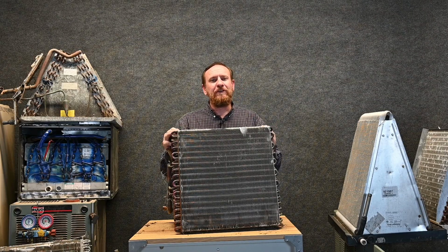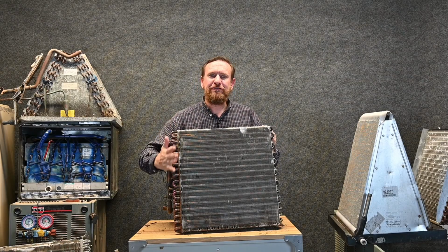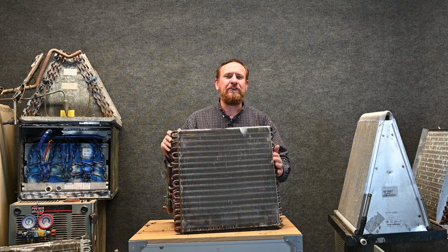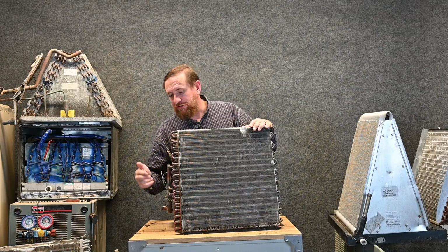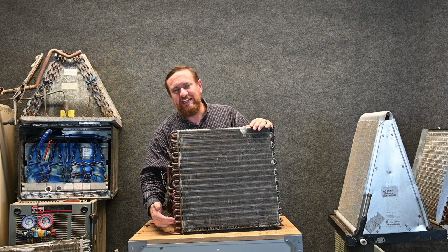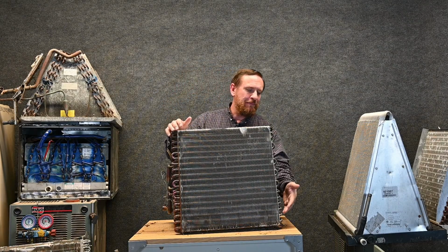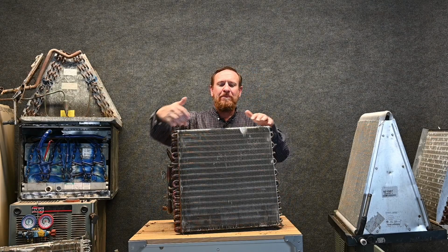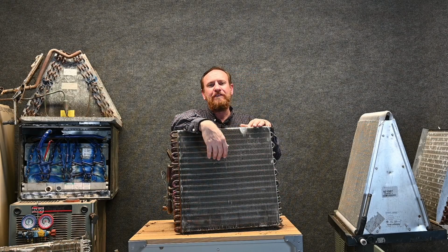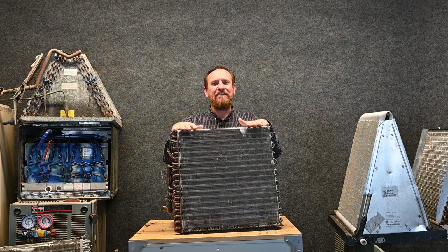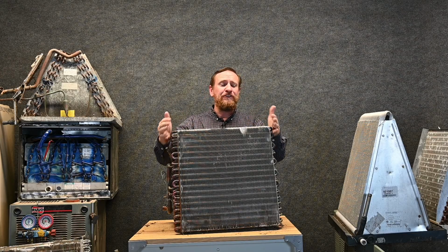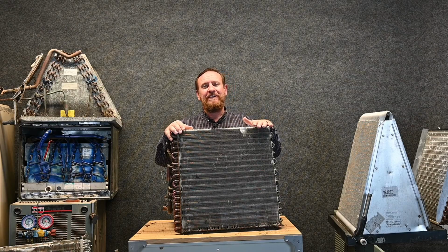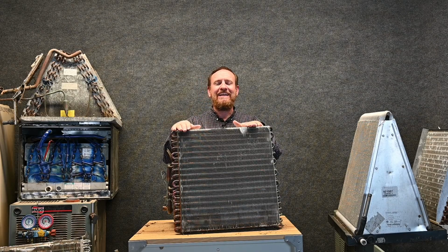Now, when we're looking for leaks in the coil, we know that we can access the front side. The back side is very difficult to leak search, but typically they'll leak right where these little U-bends are, especially where these distribution tubes enter into that evaporator coil at the bottom where you have the most electrolysis, but they can also leak right here in the very middle of the tubing. So these days anymore, you just never know where you're going to find that leak, but typically when I have a leak search, I'll look for oil at the outdoor unit, and on the indoor unit, I just immediately start leak checking that evaporator coil, because that's a very high likelihood of where my leak's going to be.